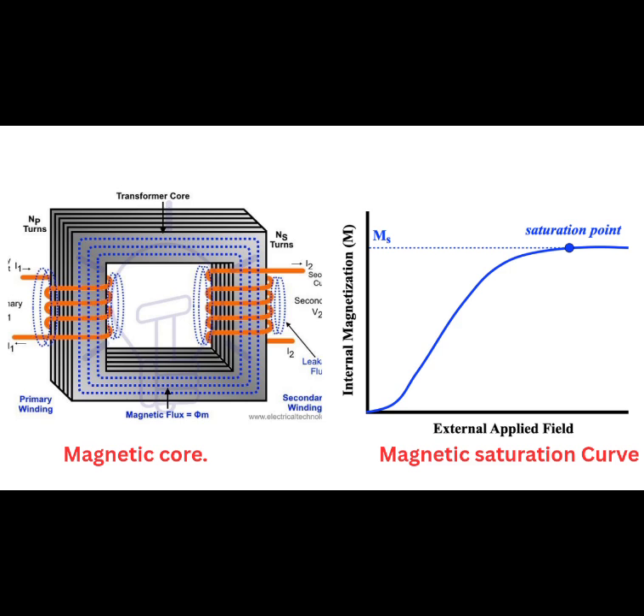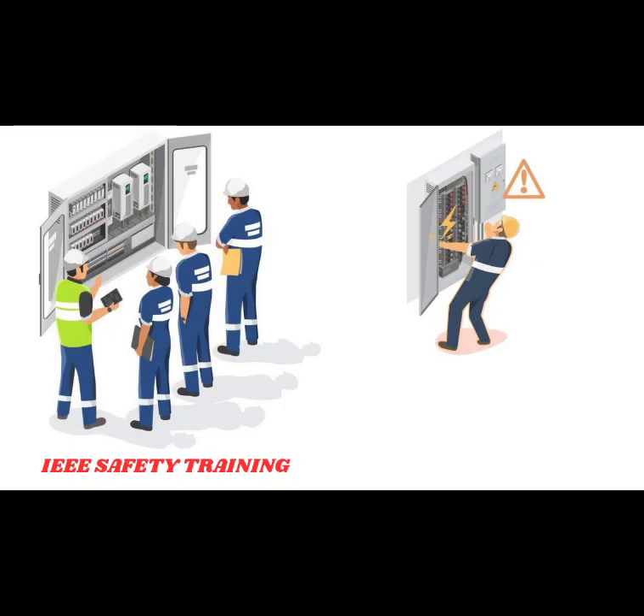Once it is saturated, the current transformer will not produce accurately scaled output, which compromises measurements and protection functionalities, leading to erroneous readings. Number four, operating safety standards. Most electrical codes and safety standards such as IEEE and IEC specifically address the operation of current transformers, emphasizing that their secondary windings should never be left open during operation.